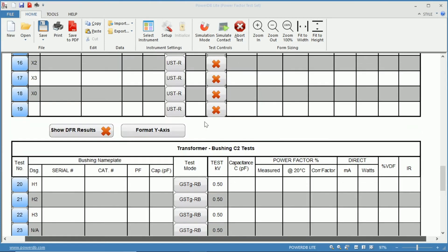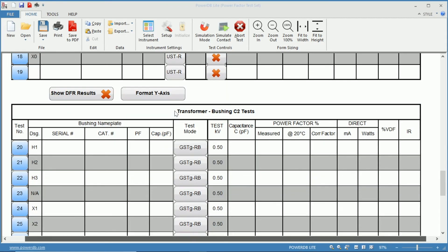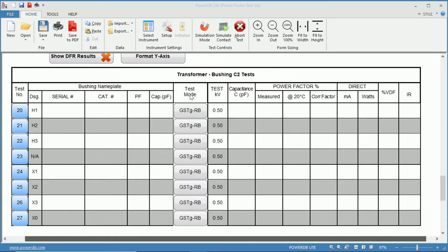Notice that the test modes are different. Here we have the UST — our ungrounded specimen test. And down on our C2, we have our grounded specimen test, guarding the red and blue leads.